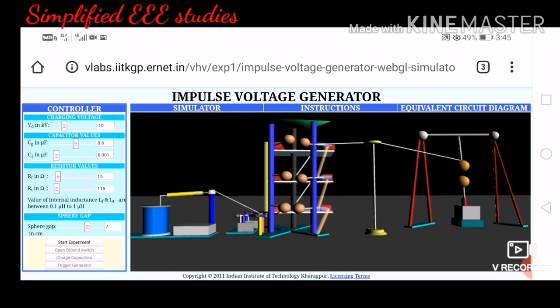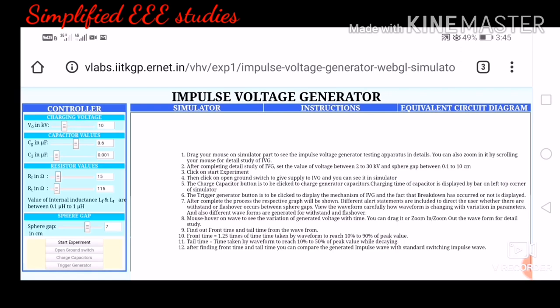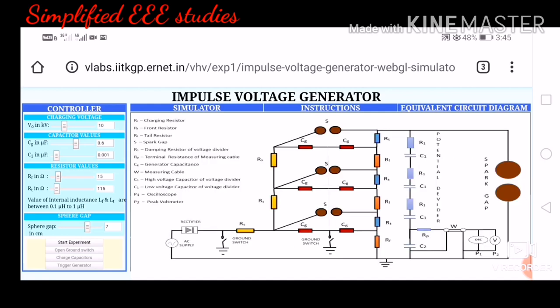If you want, click on the instruction option to read what to follow during the experiment. The sphere gap can be varied between 0.1 and 10 centimeters. The charging voltage V0 can be varied up to 30 kV. The instructions also explain how to calculate wave front time and wave tail time — I have already explained these concepts in previous videos. They have also provided an equivalent circuit diagram for reference, depicting the real-time view of the impulse voltage generator.